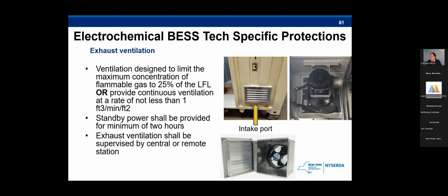And there also needs to be standby power for at least 2 hours, and it needs to be supervised by a remote station. So this is just kind of highlighting this requirement for standby power. This could apply when you see multiple types of electrochemistries in a room. And also it may be required for lithium ion as a method of explosion control, which we'll discuss in a few slides. It may be required for the responder to remove flammable gas due to a thermal runaway event, and they can just turn on the switch, which should be remote from the system. And also they have signage, which should direct responders to the ventilation fan and how to utilize it. So once again, this is not a requirement for lithium ion, but you'll likely see these installed in lithium ion projects for another requirement, which is explosion control.